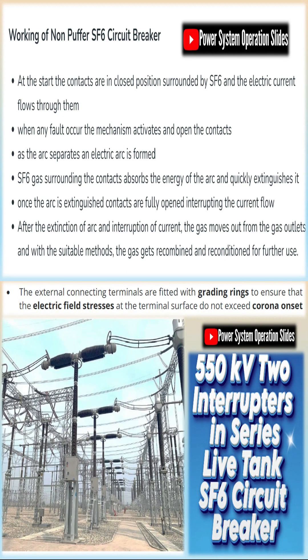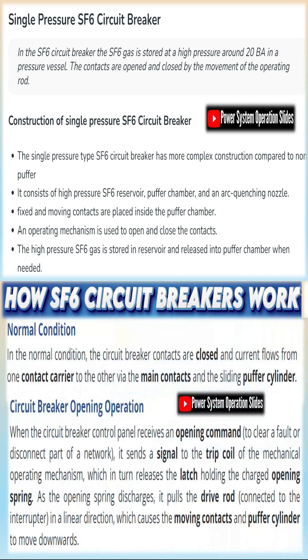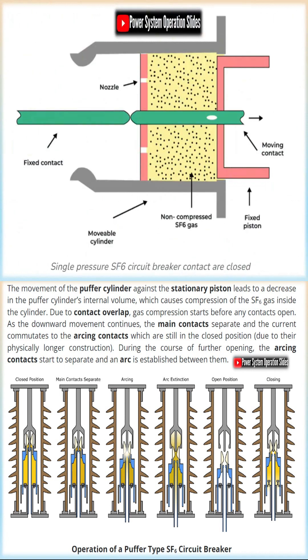The working principle of an SF6 circuit breaker involves the use of pressurized gas to extinguish the arc. Under normal conditions, the breaker remains closed and the SF6 gas serves as an insulating medium. During a circuit breaker opening operation, when a fault is detected, the operating mechanism separates the contacts, and an arc is formed and immediately quenched by a blast of SF6 gas directed through a nozzle.